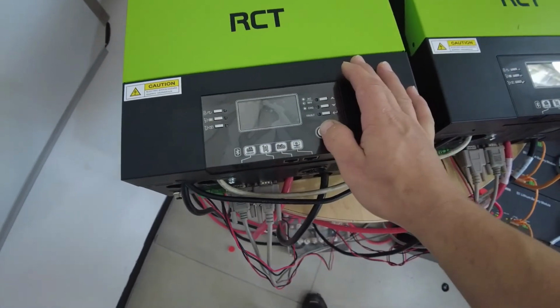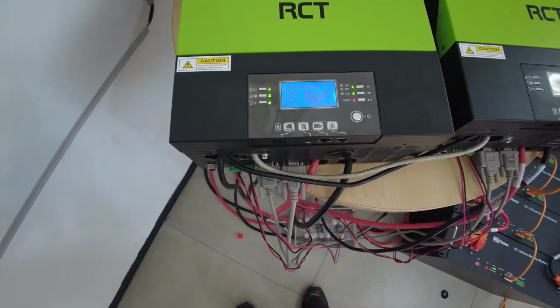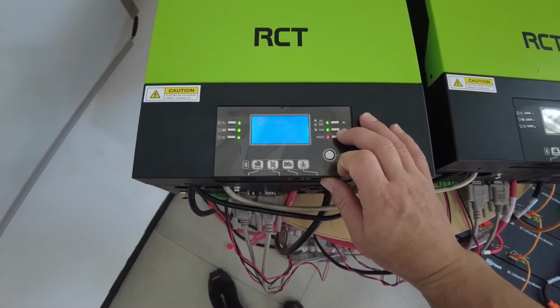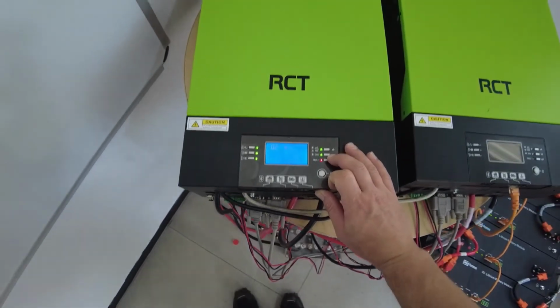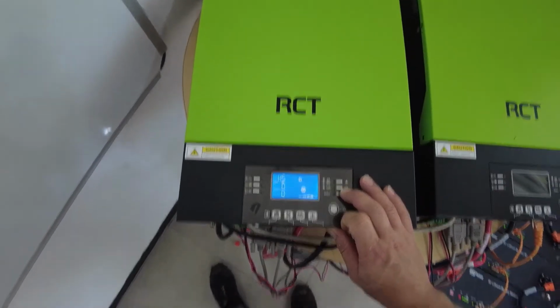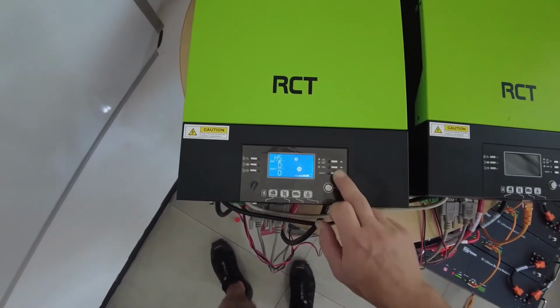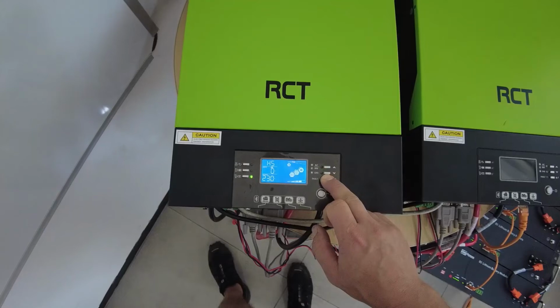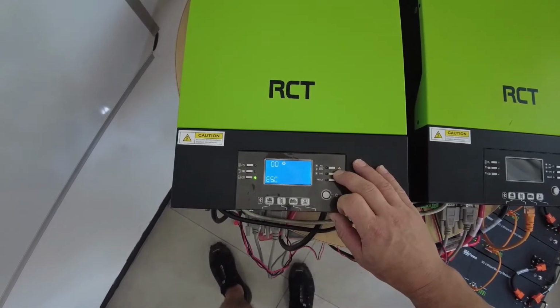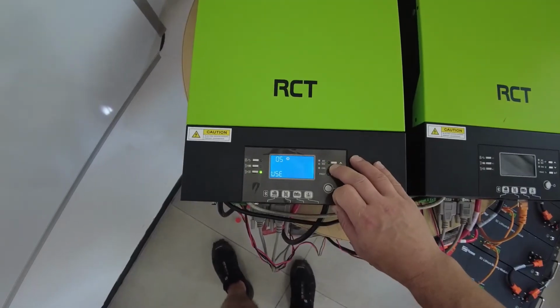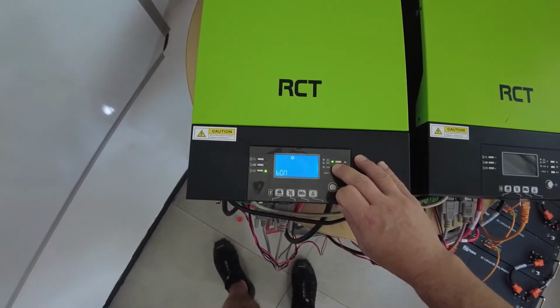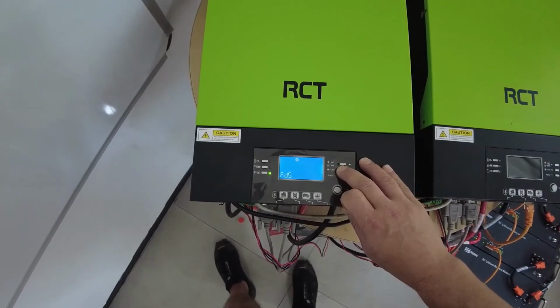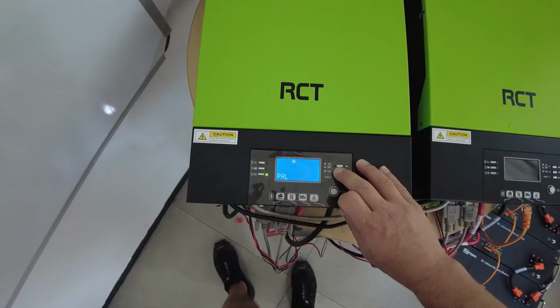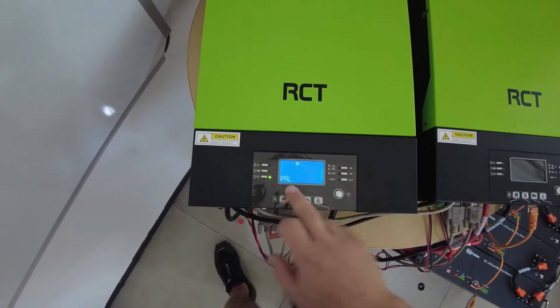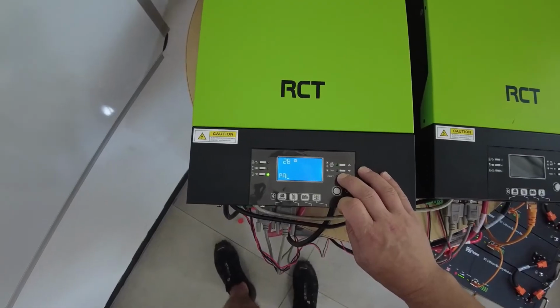Preferably do not switch on the second inverter. Let's just switch on one of the inverters at a time. Long press of the enter button till you get the 00 ESC display. Go down to number 28. Now we've already set this to PAL, which is your parallel setup that we need.